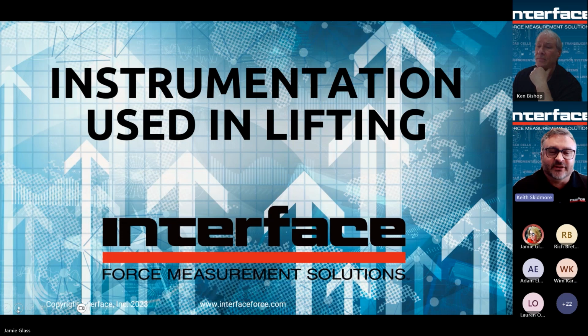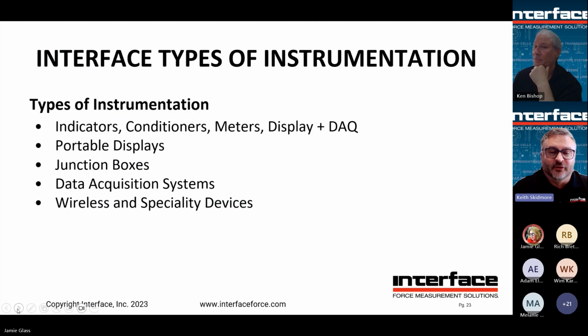All right, instrumentation used in lifting. Load cells and shackles, tension links, all those things output a signal, but the signal needs to be read or displayed by another device, which would be an instrument. So we have different types: indicators, signal conditioners, meters, displays, also data acquisition, logging, and graphing. Can display multiple load points simultaneously.